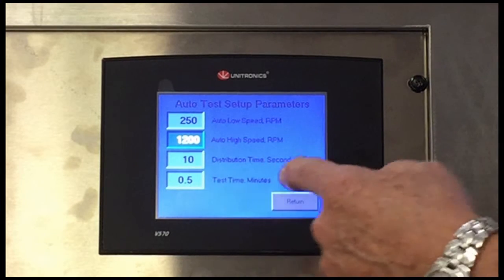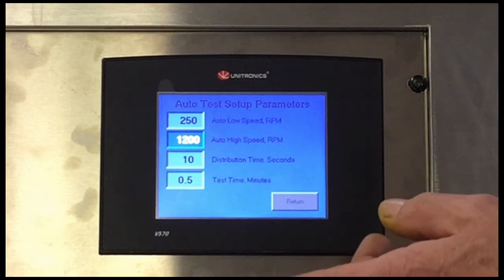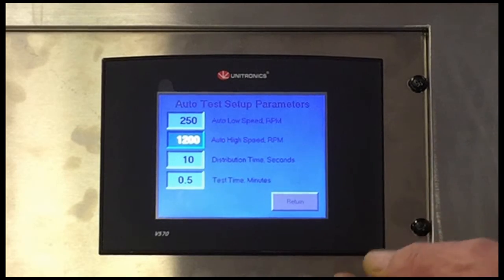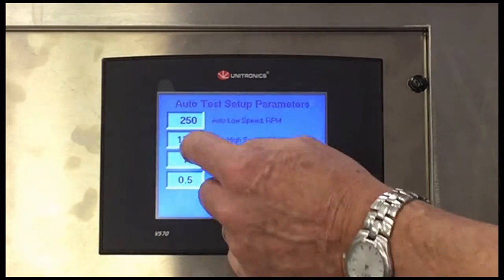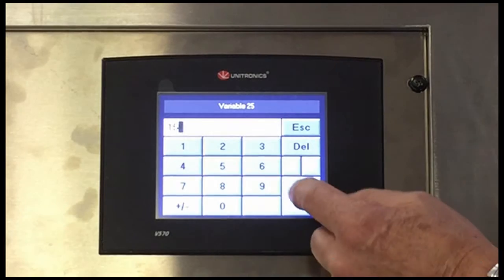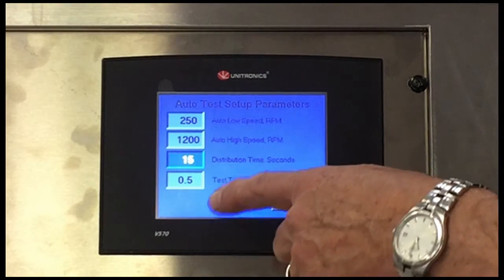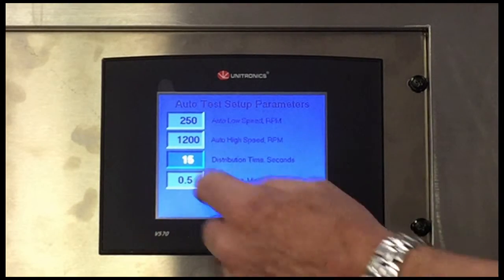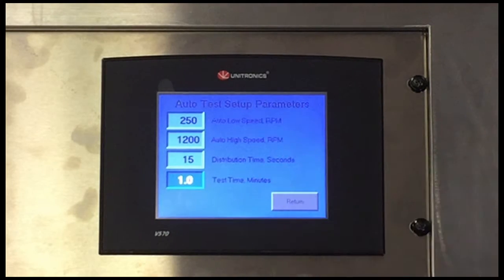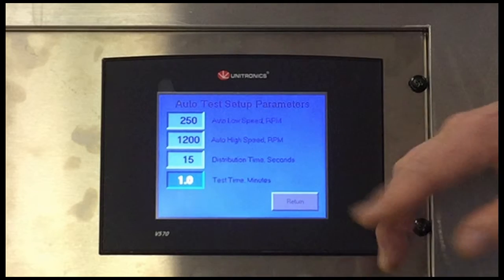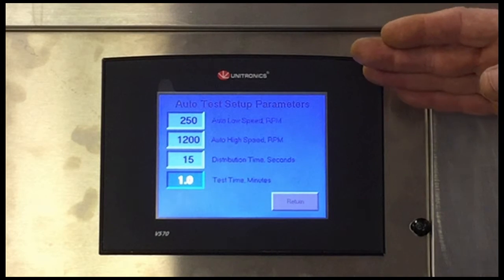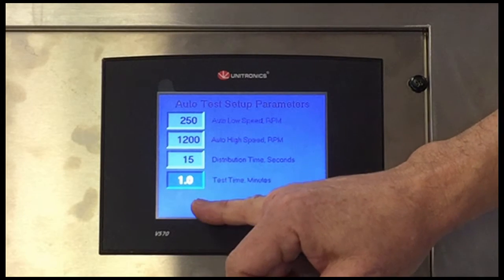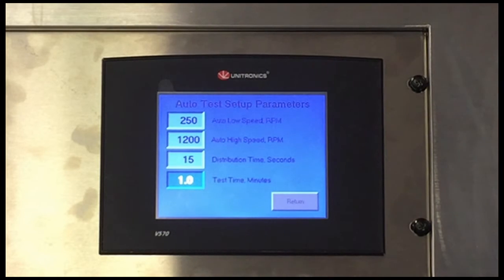Our distribution time, if you recall, when we ran that automatic test in the first segment, it distributed the ink for 10 seconds, and I make that setting here. And we ran for 30 seconds or a half a minute. Normally, these tests run for 1 minute, so we'll make that 1 minute as a test time. So what that means is when we go into the automatic mode, it's going to run for a full minute, and then it will shift down into that slow idle speed like we saw in the first segment of this.